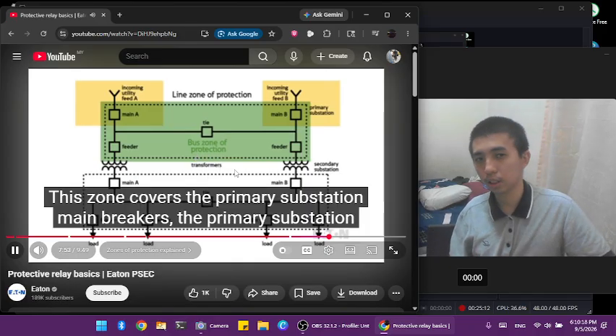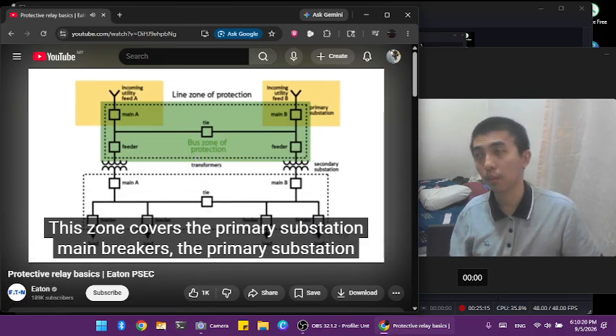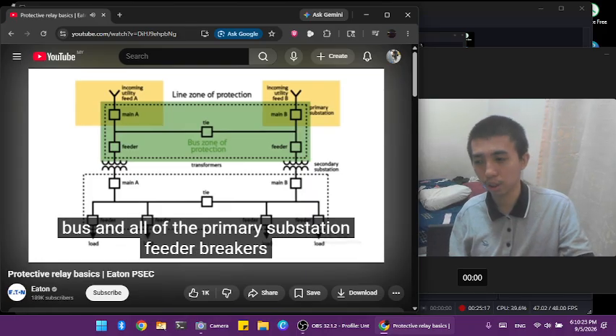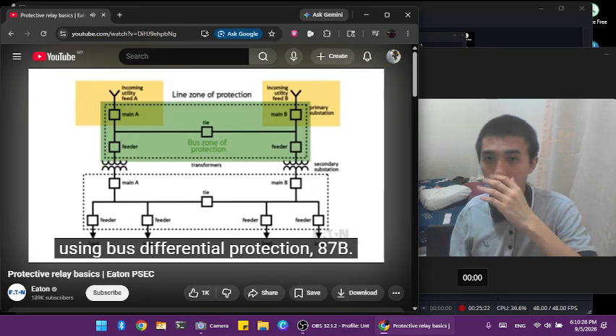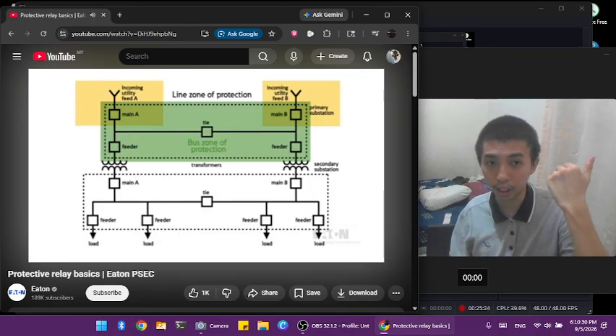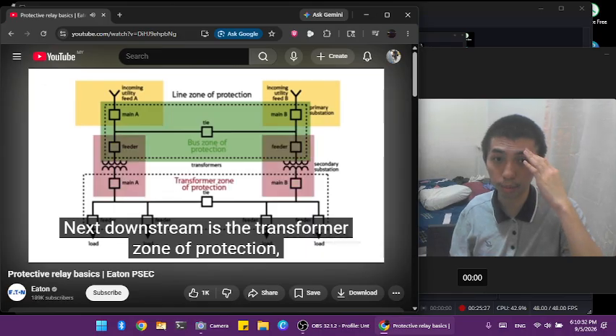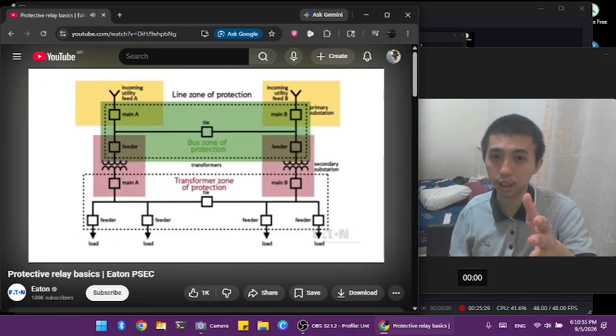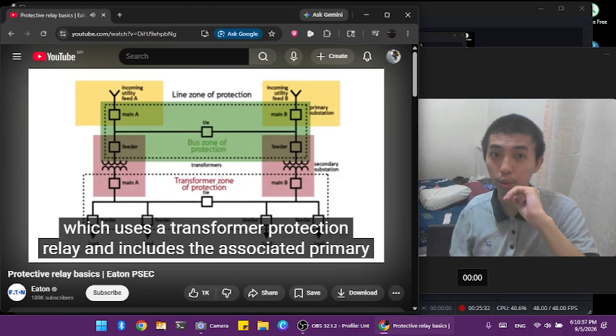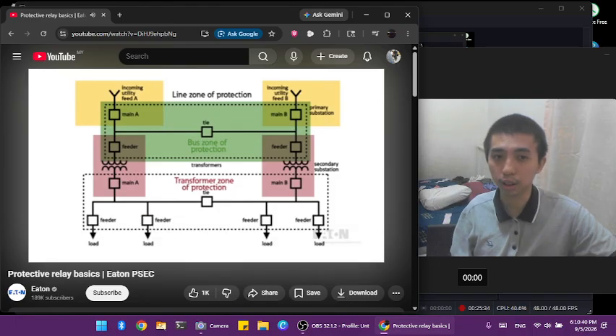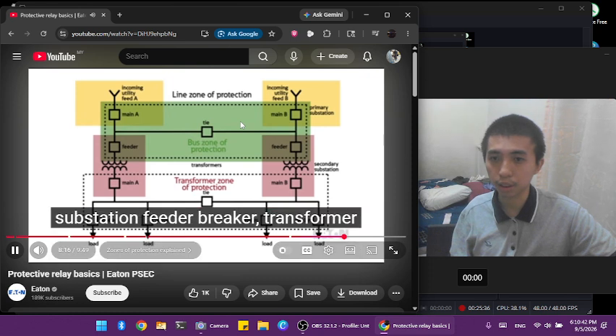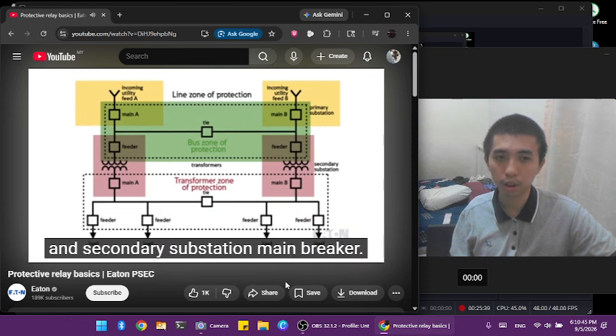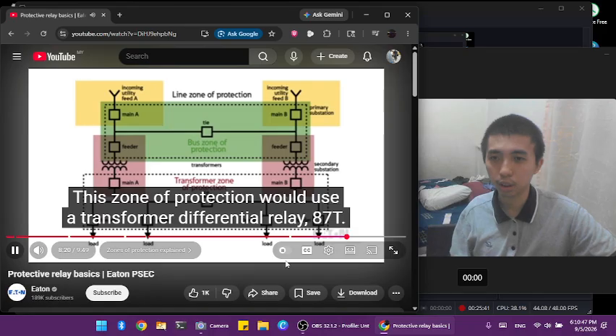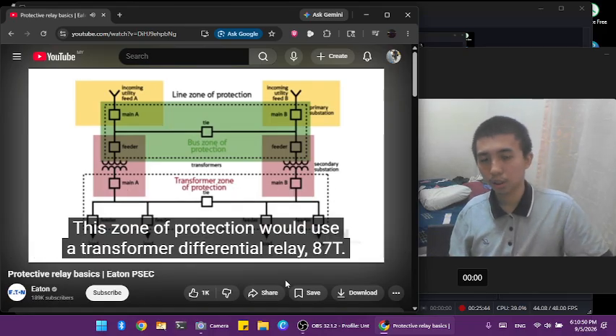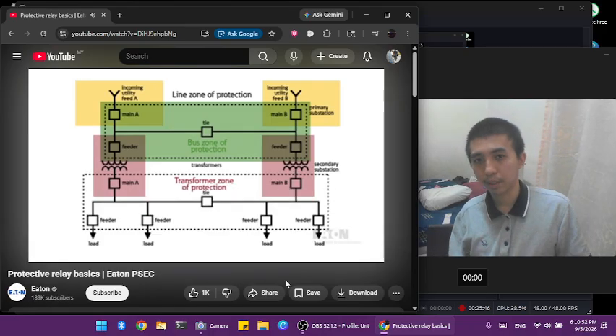Protection. This zone covers the primary substation main breakers, the primary substation bus, and all of the primary substation feeder breakers using bus differential protection 87B. Next downstream is the transformer zone of protection, which uses a transformer protection relay and includes the associated primary substation feeder breaker, transformer, and secondary substation main breaker. This zone of protection would use a transformer differential relay 87T.